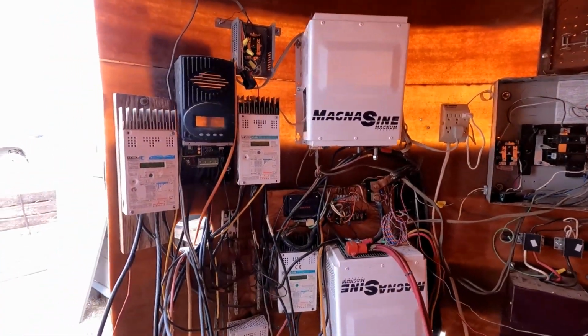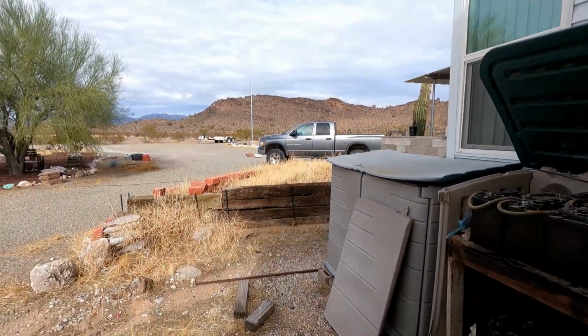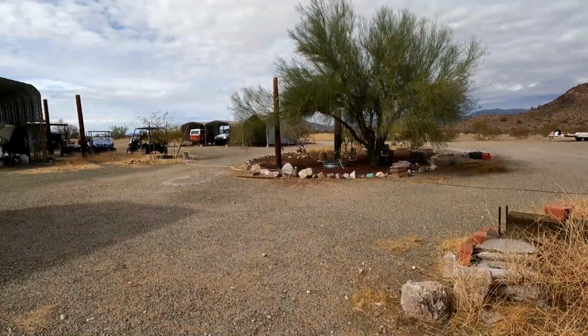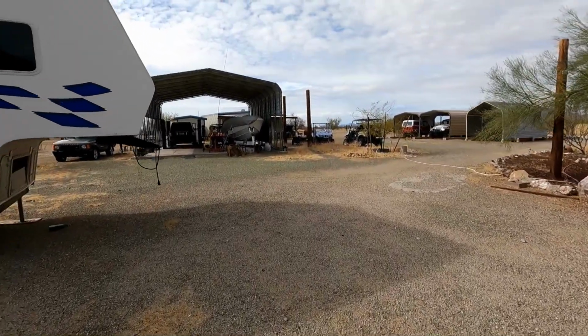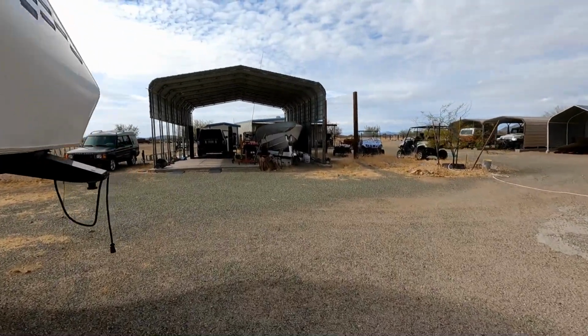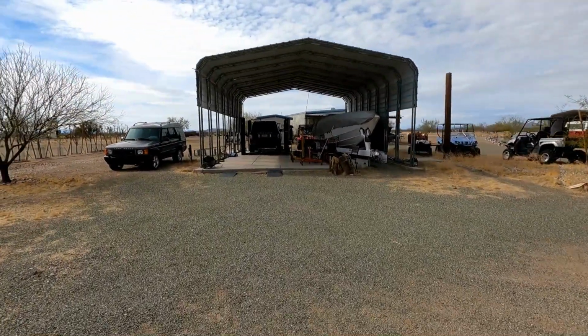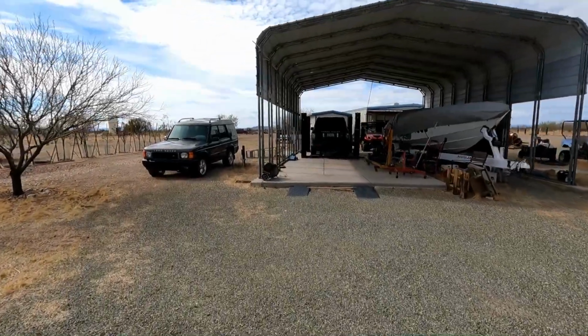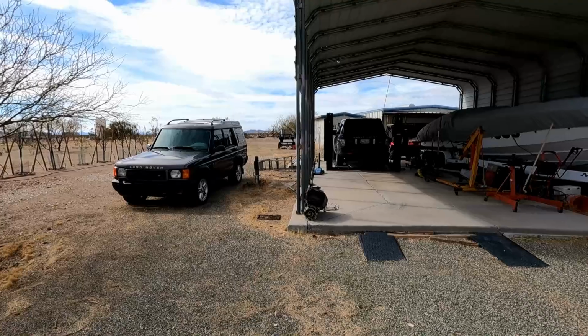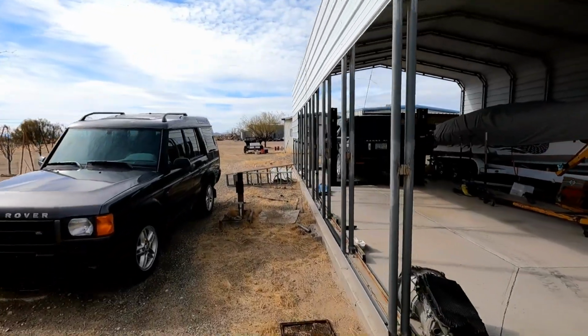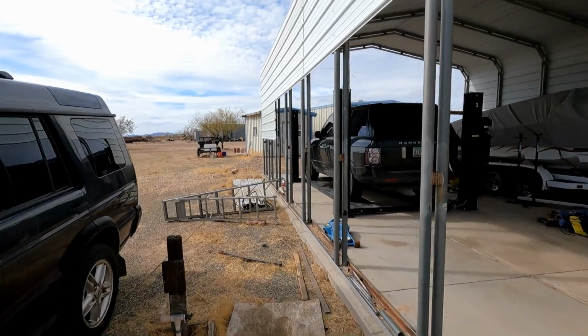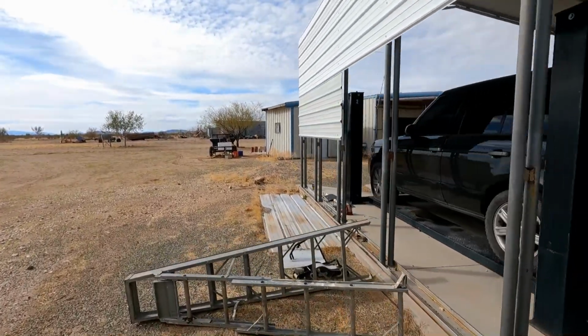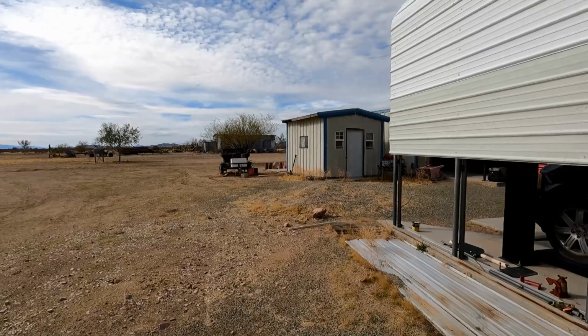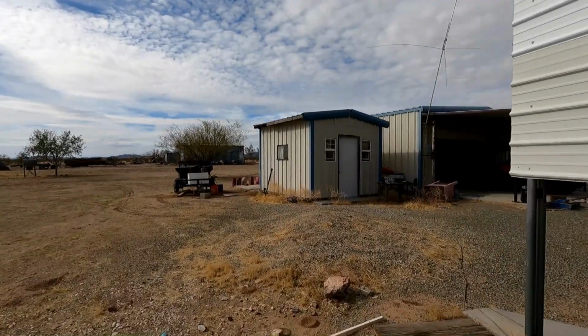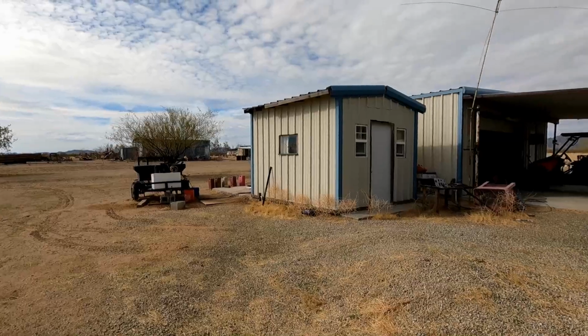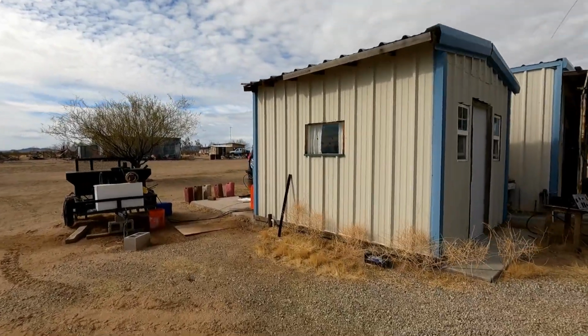And it becomes significant if, like us, you want to put the generator a good distance away from the house. And in this case, we're going to go 150 feet. The advantage being that the generator makes a certain amount of noise that you would really prefer to hear a minimum of in the house. We've got a little added advantage that even at 150 feet away, we've got a shed here that blocks the generator also. But remember that the power got interrupted over there at the house.